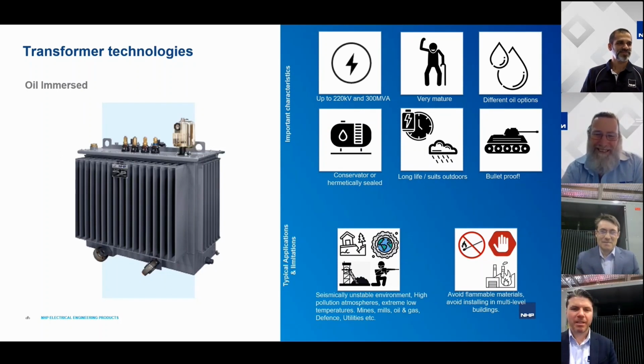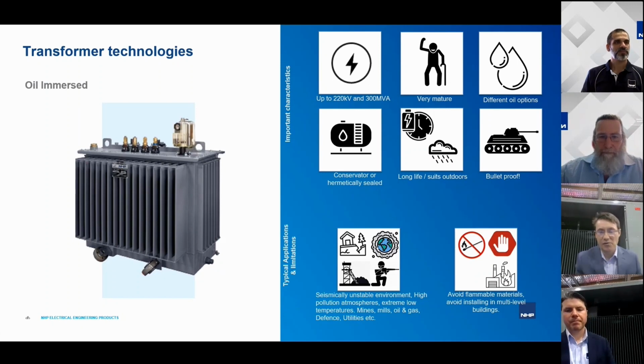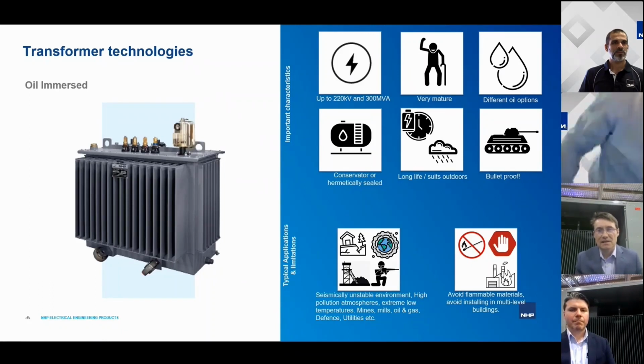All right, well, let's quickly have a look at the typical applications and then some of the obvious limitations when it comes to oil transformers. Dimitri. Yes, so the typical applications are outdoor. The transformers can be used pretty much everywhere. They have advantages in outdoor applications because, like we said, the HV components are fully protected. They're inside the steel tank, so it's not sensitive to any corrosive environment. Of course, the paint has to be of a proper standard to withstand those environments, but that is achievable. So for dusty applications as well, the oil transformer certainly has an advantage over cast resin. Therefore, they're so popular in the mining industry.